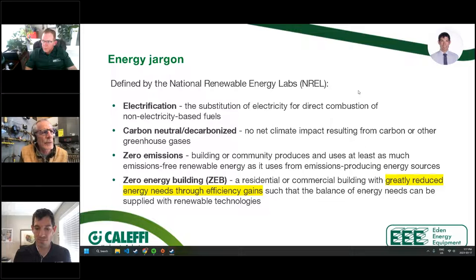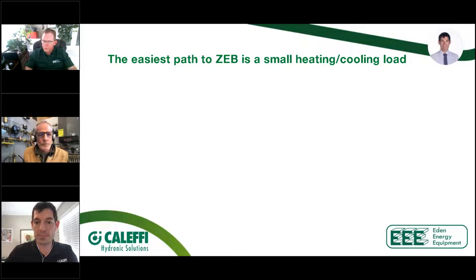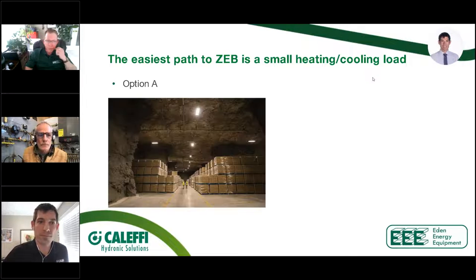the building. And I think it was issue number 25, Max, that we talk about reducing the supply temperature and water temperature. Lowering water temperature in existing buildings. So if you have a building with fin tube that was designed at 180 degrees, now what are you going to do? So there are tricks that can be done, but do that in conjunction with lowering the load on the building, upgrading the insulation or the windows, perhaps something to get the number as low as possible. And then start doing your heating and cooling design. Yeah, great comment. Totally agree.